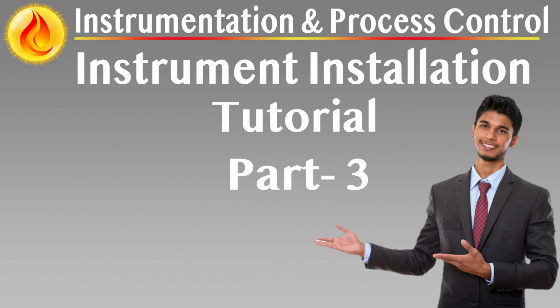For less severe services where fouling is not a concern, equalizing lines may be introduced to allow in situ zero and span calibration at full process pressure. These systems offer enhanced accuracy and allow for re-zeroing without removal, particularly valuable in high-pressure or critical level applications.